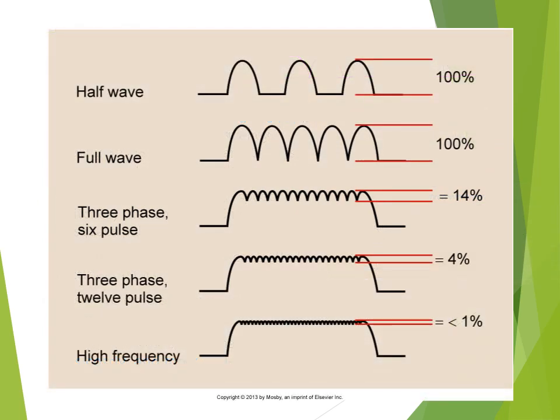So taking a look at ripple, which is going to change from 0 up to the kilovoltage that we have set. So this is 0, and that's why it's going to be a 100% change. Half wave and full wave both do that. Again, half wave is called single phase 1 pulse, and full wave is called single phase 2 pulse, but it's 100% change. Now, on the other hand, 3-phase 6 pulse doesn't start down here at 0. It's going to start up here, and so this number is actually 14%, but it's not going to change very much.